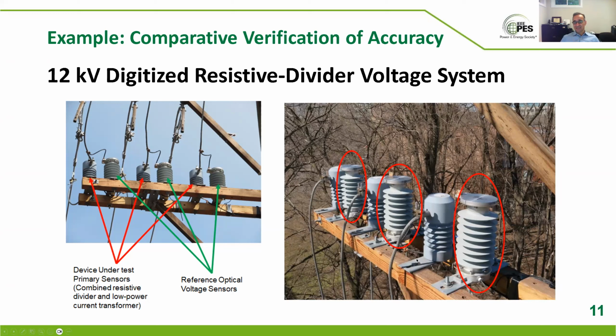But all of these interdependencies and field dependencies made a case for, hey, we think this is good, but we need to verify accuracy and calibrate it in the field. For that purpose, they put in for a few weeks, actually ended up being a few months, some optical voltage sensors that are optically isolated, only fiber, passive up here with electronics at the ground potential, which natively provides sampled values, and they're both time tagged, so they can apply the same primary voltage to both sensors. Basically, the optical is the reference, and the other sensor, together with its digitization and everything, is the digital sensor under test. So this is a local synchronized waveform measurement.